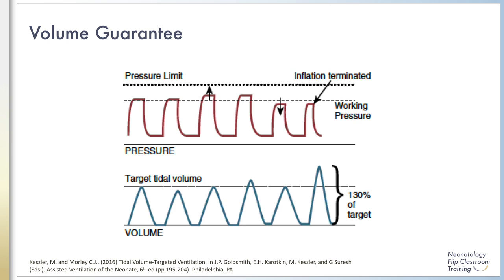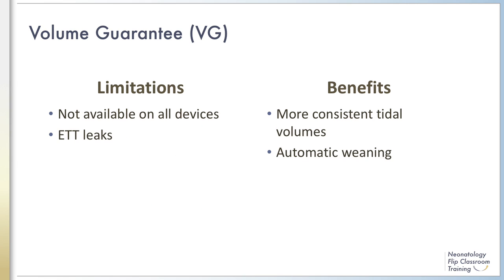This means it may take a few breath cycles to reach the targeted tidal volume if there is a significant change in patient lung compliance or inspiratory effort. Looking at the waveforms on this slide, the tidal volume for the second breath is below the target volume, so on the next breath the pressure is increased to reach the target volume. On the following breath, the volume is above the target, so the pressure is decreased. The dotted line at the top is the set pressure limit — inflation is terminated if the pressure reaches this limit, even if the set tidal volume has not been reached.